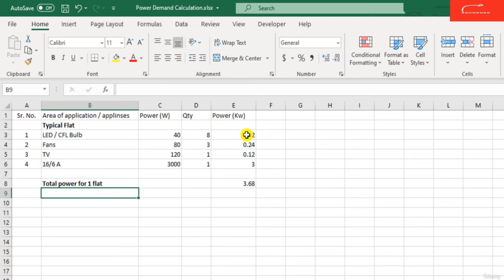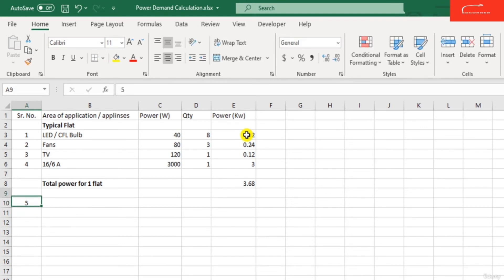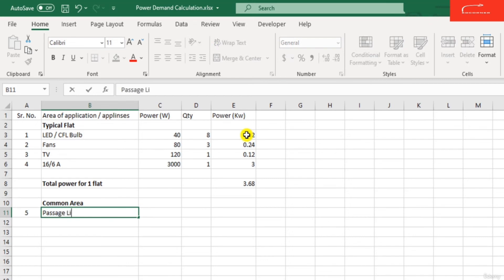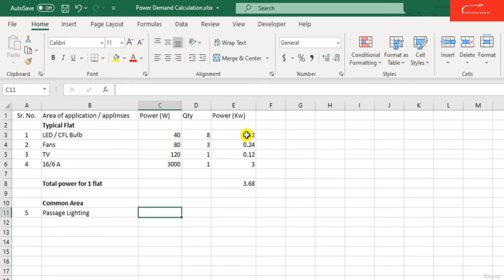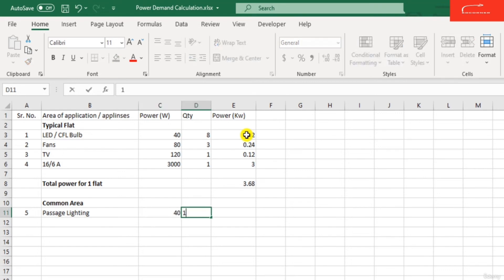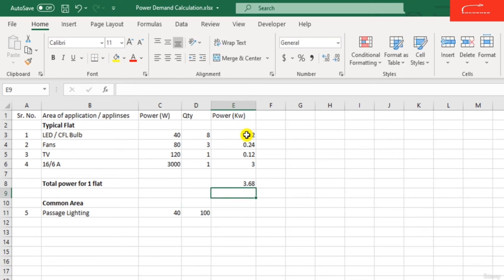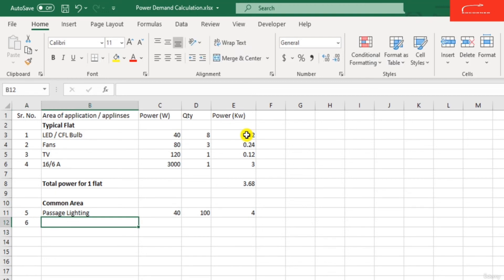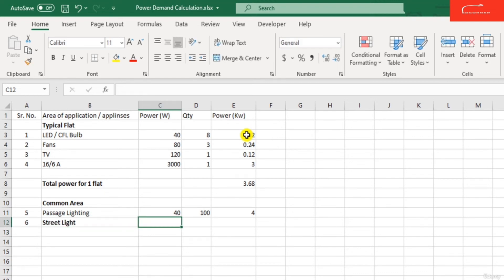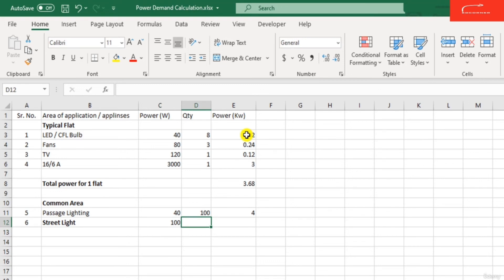Now we need to calculate the common area power demand — such as lift, passage, corridors, etc. For the passage lighting: 1 bulb requires 40 watts, and if the entire building has 100 bulbs in the passages, the power required is approximately 4 kilowatt. Next, for street lights or compound lights, each street light bulb is 100 watts with a total quantity of 20, giving 2 kilowatts required for street lighting.